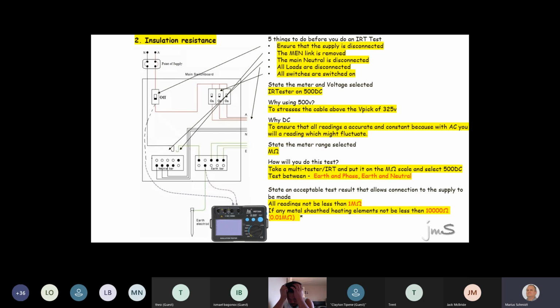To recap, what instrument will I use to do an insulation resistance test? IRT tester, insulation resistance tester. If I give you the multifunction tester, you know that big instrument, you just make sure that you test megohms. Take it to insulation test. How many volts will I use? 230 or 500 volts? AC or DC?